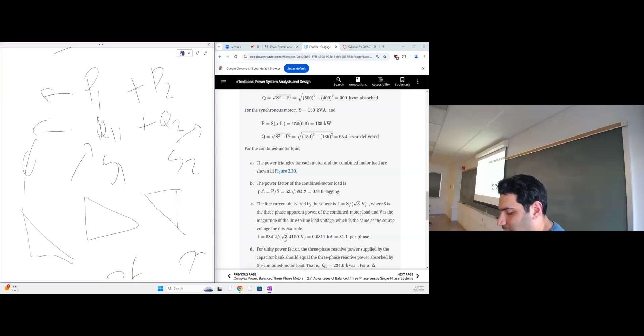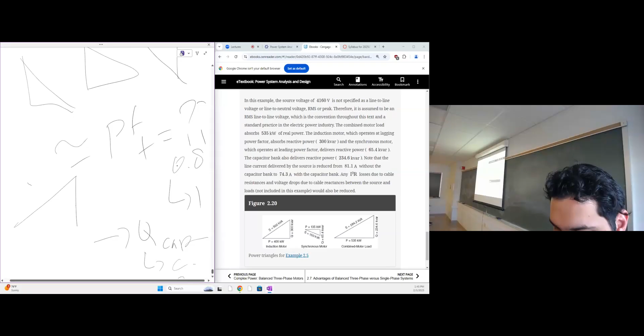It's 81.1 amperes per phase. To make the power factor 1, we would need to eliminate this 234.6 kVAR, since this is the power triangle, and this is the angle I have. If the power factor is 1, meaning S equals P, then this triangle will be aligned. This is a very ideal case where S equals P here, and the Q disappears.